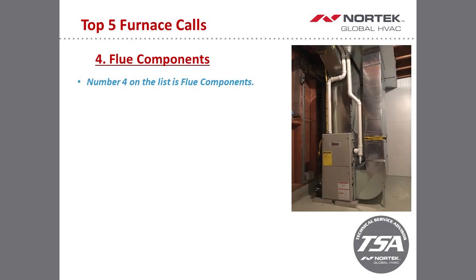The next thing that we'll take a look at here is flue components. Now, we get questions on this, like, does this furnace require 3-inch pipe? When should I go to 3-inch pipe? We also get questions on, with this furnace BTU, will I be okay on 2-inch pipe for the amount of length that I have? Again, all that can be found in either the tech spec of the furnace, which is available on our literature website, or in the install instructions as well.